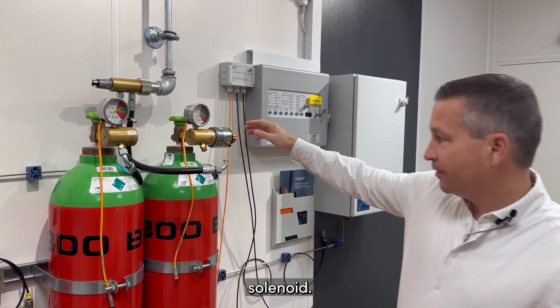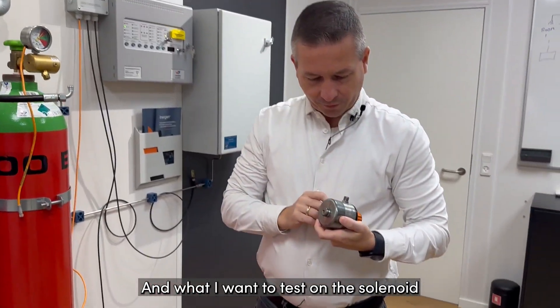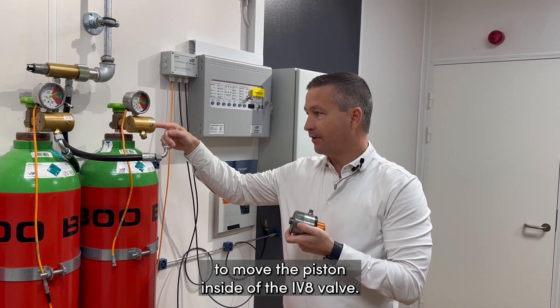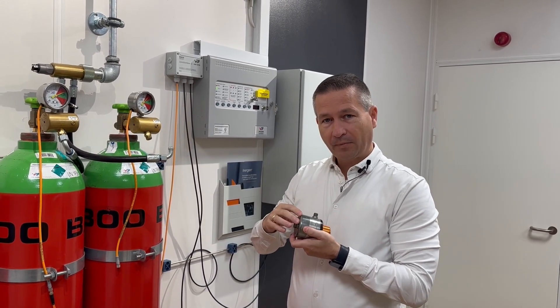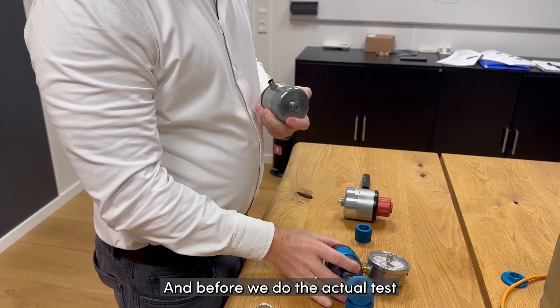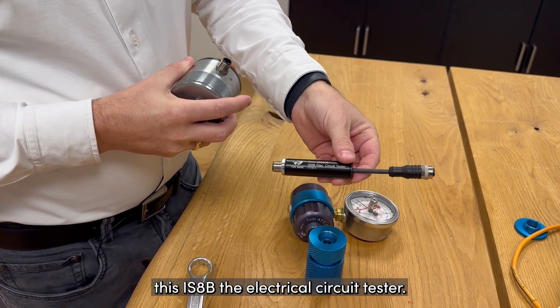Now I can dismount my solenoid. What I want to test is that when we activate the solenoid, the piston will come out with a force, and that force should be able to move the piston inside the IV8 valve. To measure the output of this piston, we have a testing tool. Before we do the actual test, we have in our toolkit box this IS-8B electrical circuit tester.